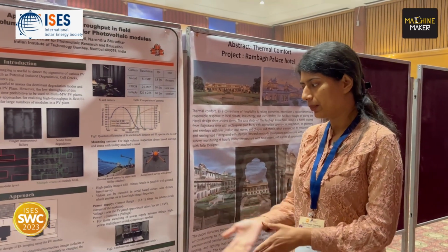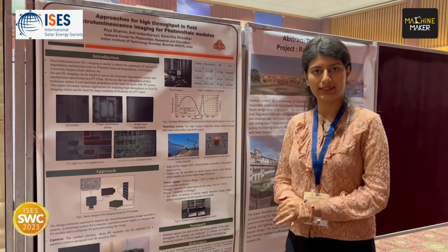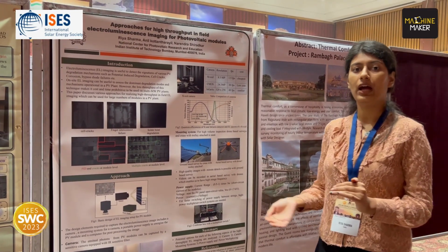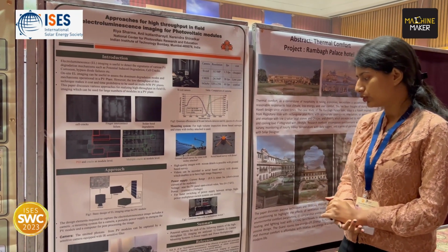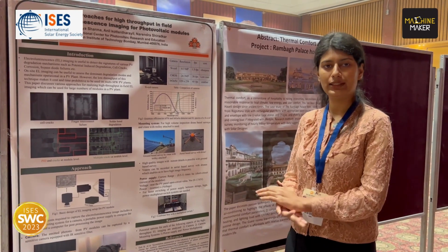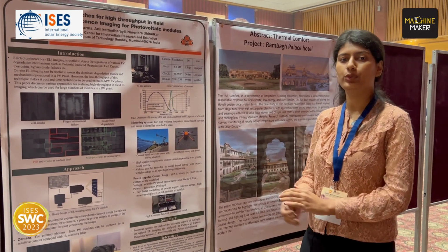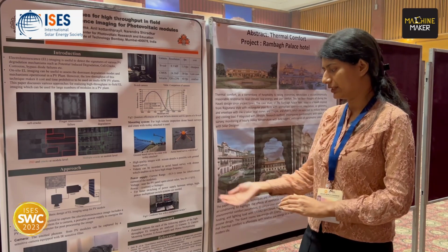And in the end, the power supply that is used to energize these modules is needed. There is a need to have a large wattage power supply. So in this, a multiplexer switch can be used at the combiner boxes, where the modules can be switched between the different strings with the power supply.